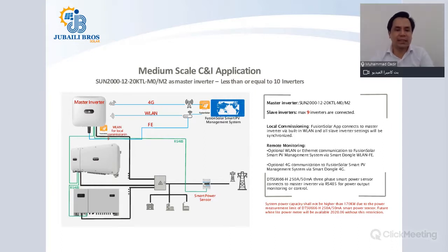Medium scale C&I application. When you are using a 12 to 20 kilowatt inverter as the master inverter, and you have less than or equal to 10 inverters, then since the master is compatible with the dongle, you can connect the dongle directly to it. It will receive the data of the rest of the inverters as well, and send it to the FusionSolar cloud.